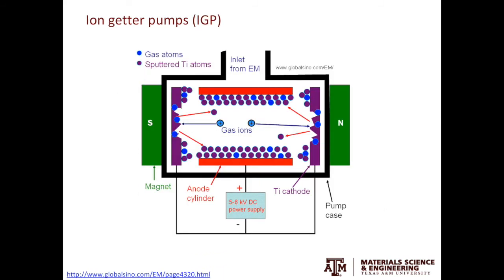The last type of pump is the ion getter pumps. Similar to the oil diffusion pump and different from the rotary and turbo molecular pumps, there is no moving part in the ion getter pumps. You have a cathode made from titanium, and an electron beam can emit from the cathode to ionize the gas molecules. The ionized gas molecules will then sputter titanium and deposit on these two plates. During the deposition process, the gas will be embedded or trapped in the titanium layers.